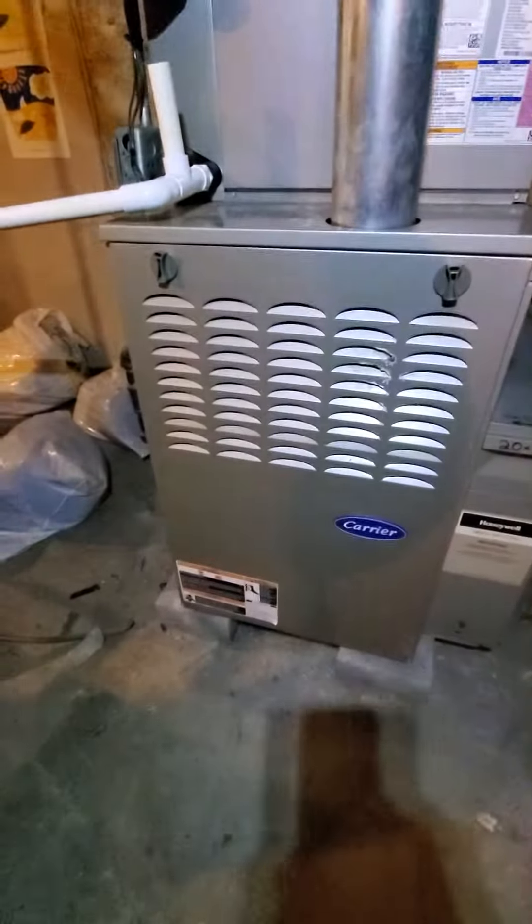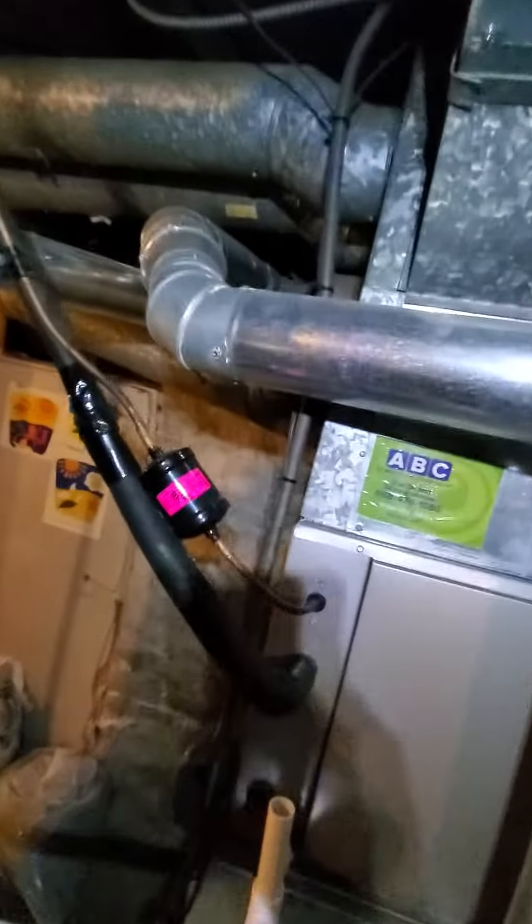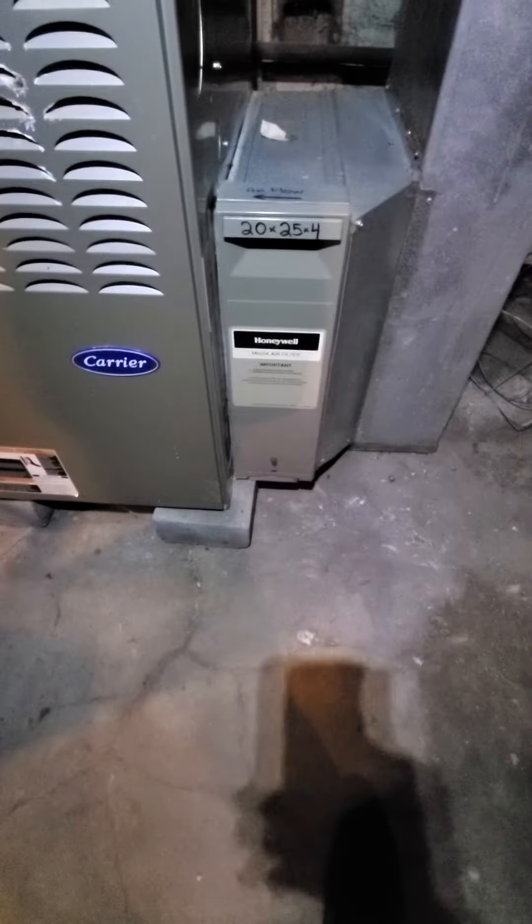The gist of the equipment: 21-inch cabinet, 110,000 BTUs, 80% efficiency, single stage. Your return drops coming in at 18x8, and then it widens out. You've got a media filter in there, 20x25x4.